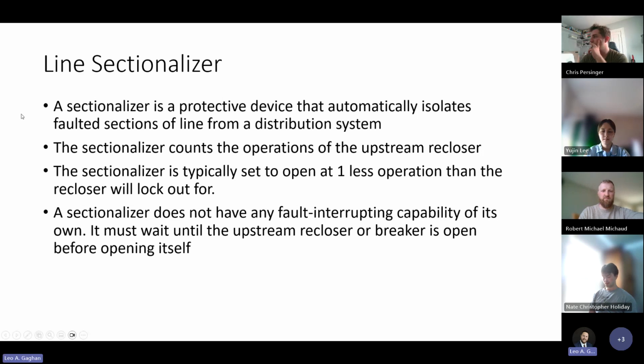So it can do some more functions. It can count the number of operations of the upstream recloser. It can figure out we lost voltage, we got it back, we lost voltage, we got it back. It can tell how many shots the upstream device is at and make decisions based on that. So it's typically set to open at one less operation than the recloser upstream would lock out for.